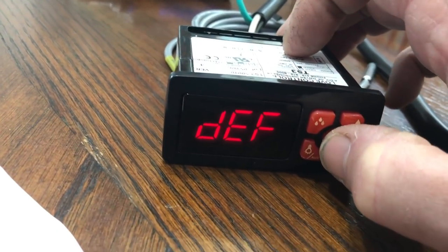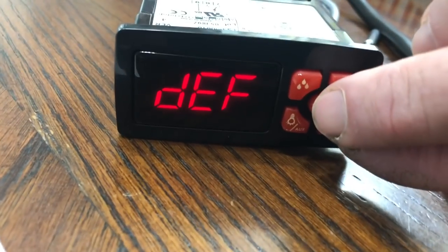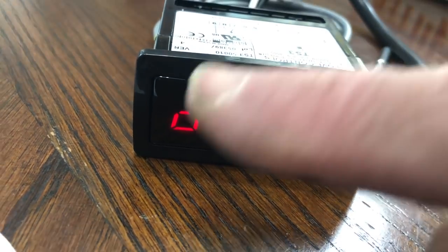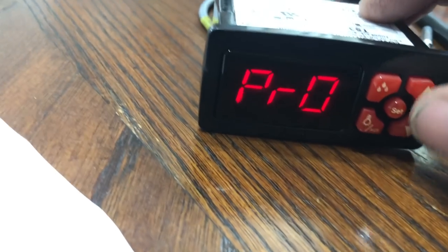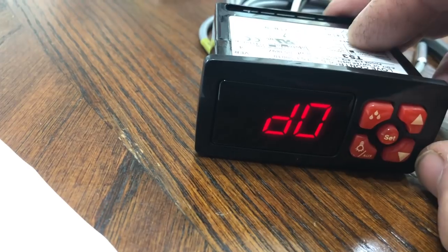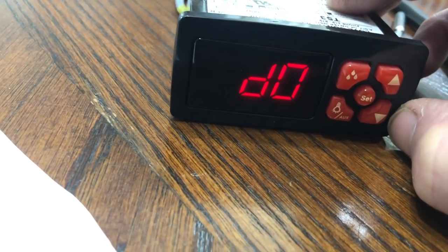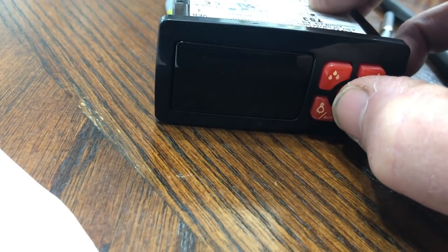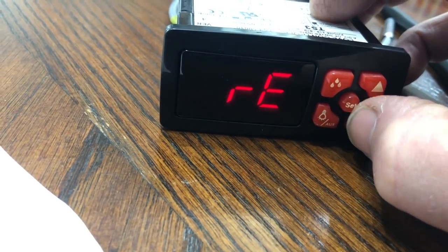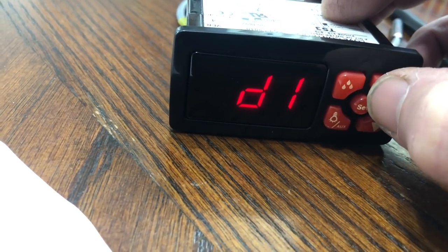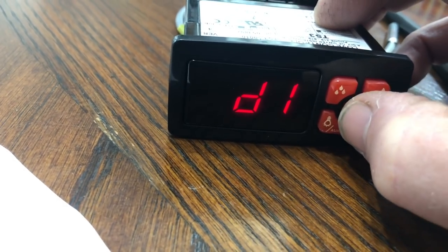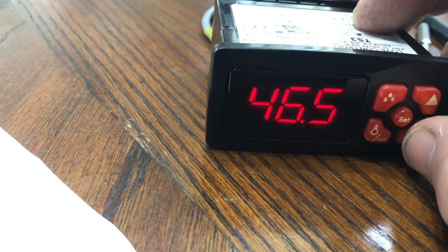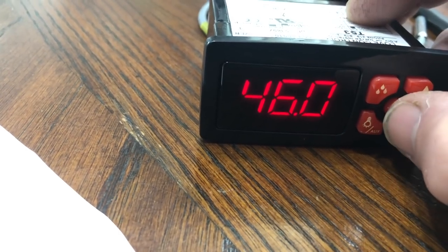Now we can get into the defrost ones. So if I hit these two again right here at the same time, it takes you back to the sub parameters when you get into these. That's the pro. So we're going to set to go into the defrost mode right there. And RE is defrost and cooling. That's what I want. D1 is temperature at which defrost will stop. I set that at 46 and a half degrees. You could probably set it lower to like 46.